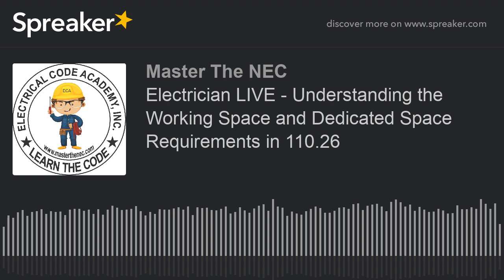Okay, so it also gives us an informational note that says, hey, be aware that there is a standard for electrical safety in the workplace, and it's an informational note, so it's not enforceable, but it is a real good document to familiarize yourself with. Get a copy of it and just have it handy. It's all about safety, and at the end of the day, everybody wants to go home at the end of the day, right? We all want to be safe. So 110.26(A)(1), which is dealing with the depth of the working space. Let's dig into that first. It says, the depth of the working space in the direction of the live parts.